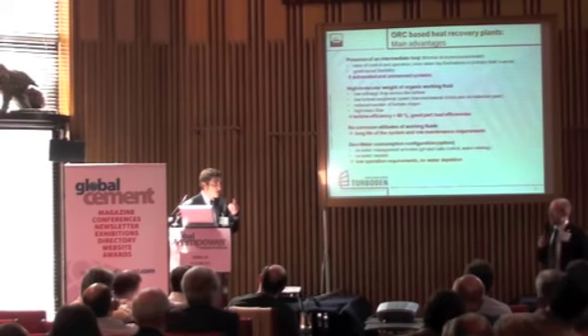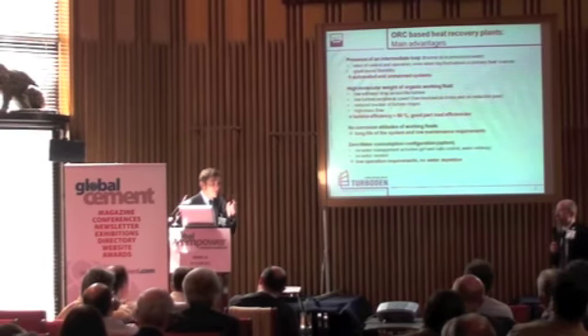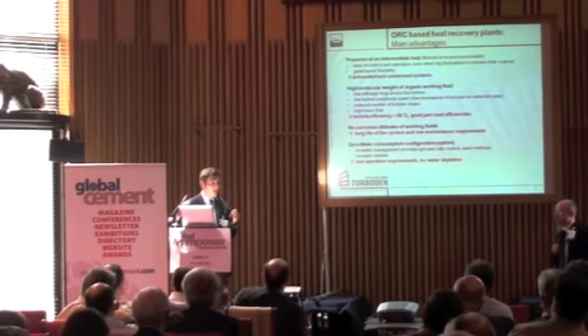Just a note on the seal. Entropy drop also means speed. In an organic system, the speed of the fluid is very much slower than steam. Steam is a small molecule and runs very fast, so you really have to take care about sealing, which can also be erosive because of how fast it goes. For organic compounds, this point is much more easily addressable.